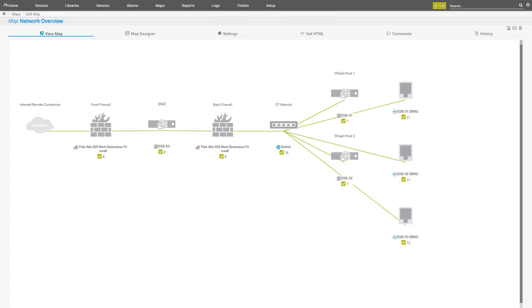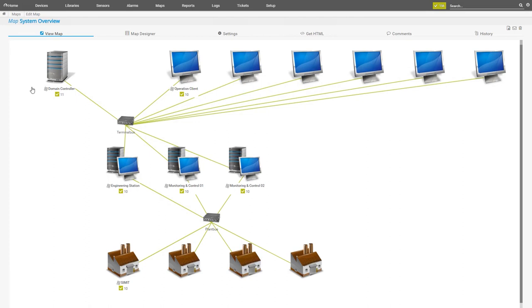As the most important data is located in the production plant itself, I created a detailed overview that shifts the focus away from the hardware to the virtualized layer of the system. Our virtual machines are shown here with their access to the plant networks. In the center, we can find the core with engineering and monitoring and control stations. Below, the control level simulated in our demo model via SIMIT. Above, the domain controller and the operator stations. For our demo plant, we have only set up one operator station, so you can see a status at one station. We can directly jump to the overview of the device by clicking on the respective icon and see exactly where an error comes from.